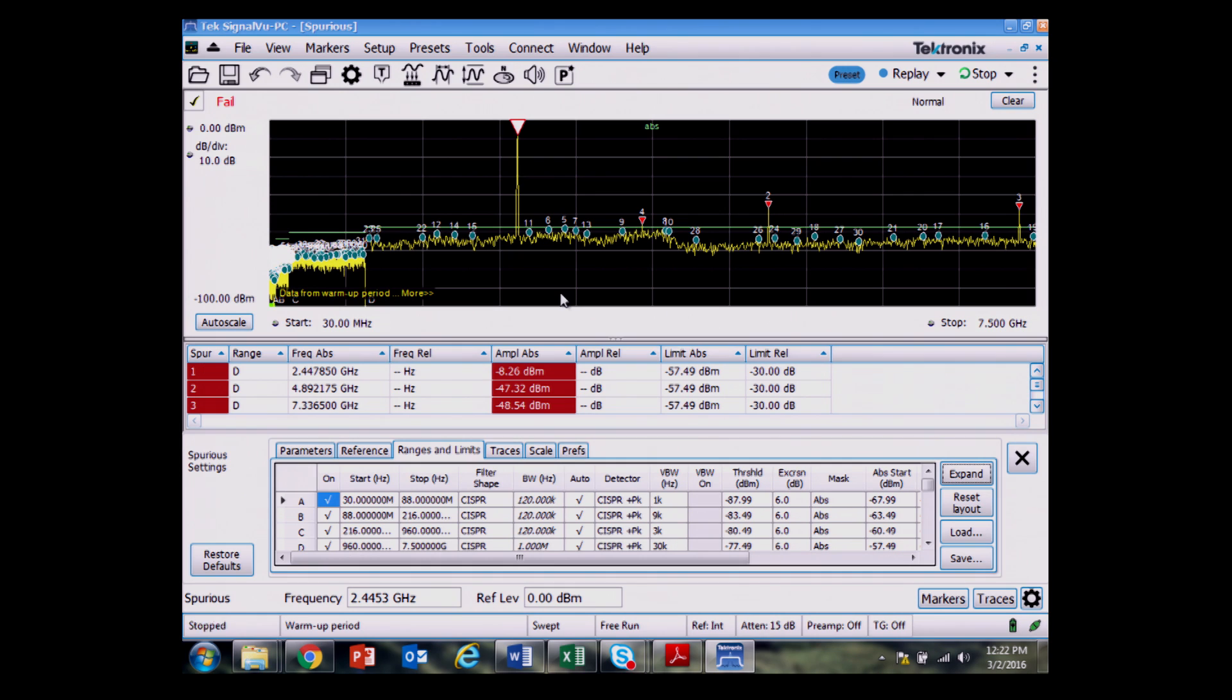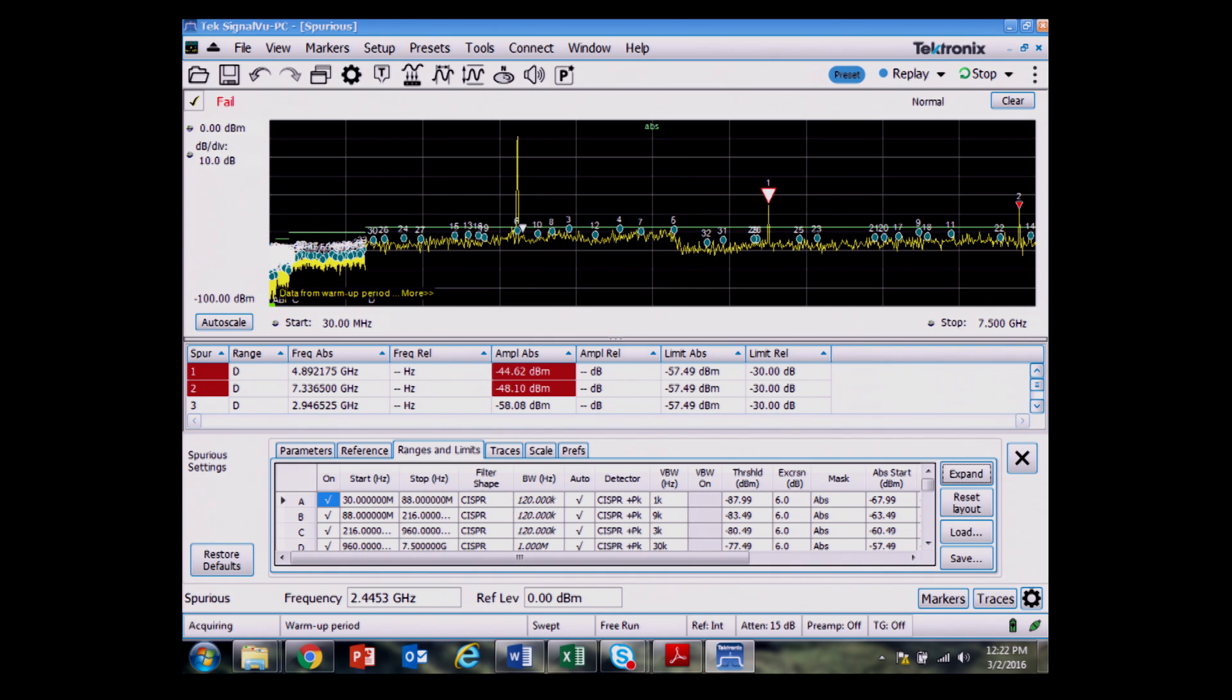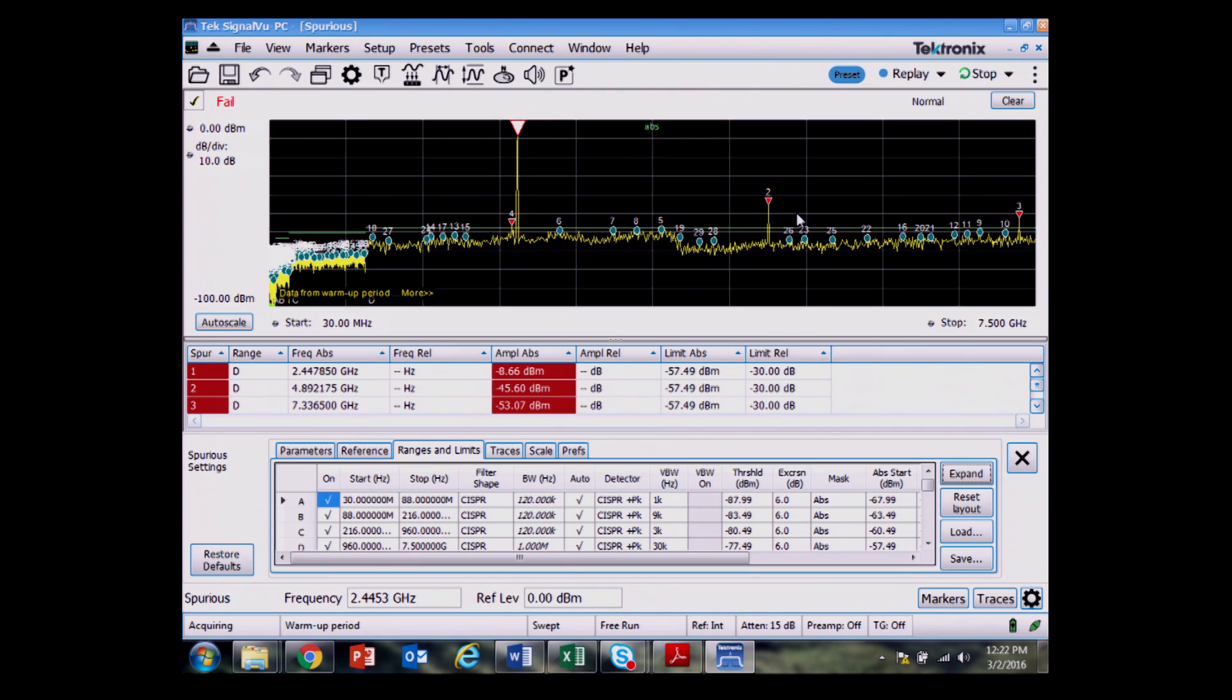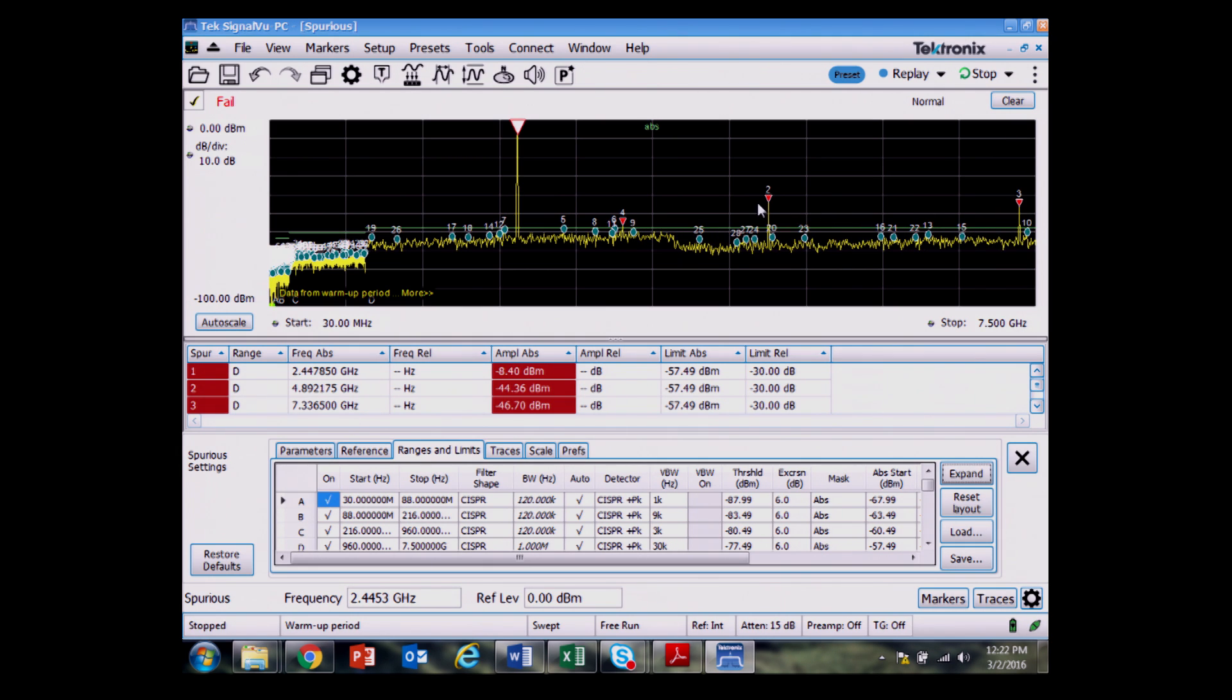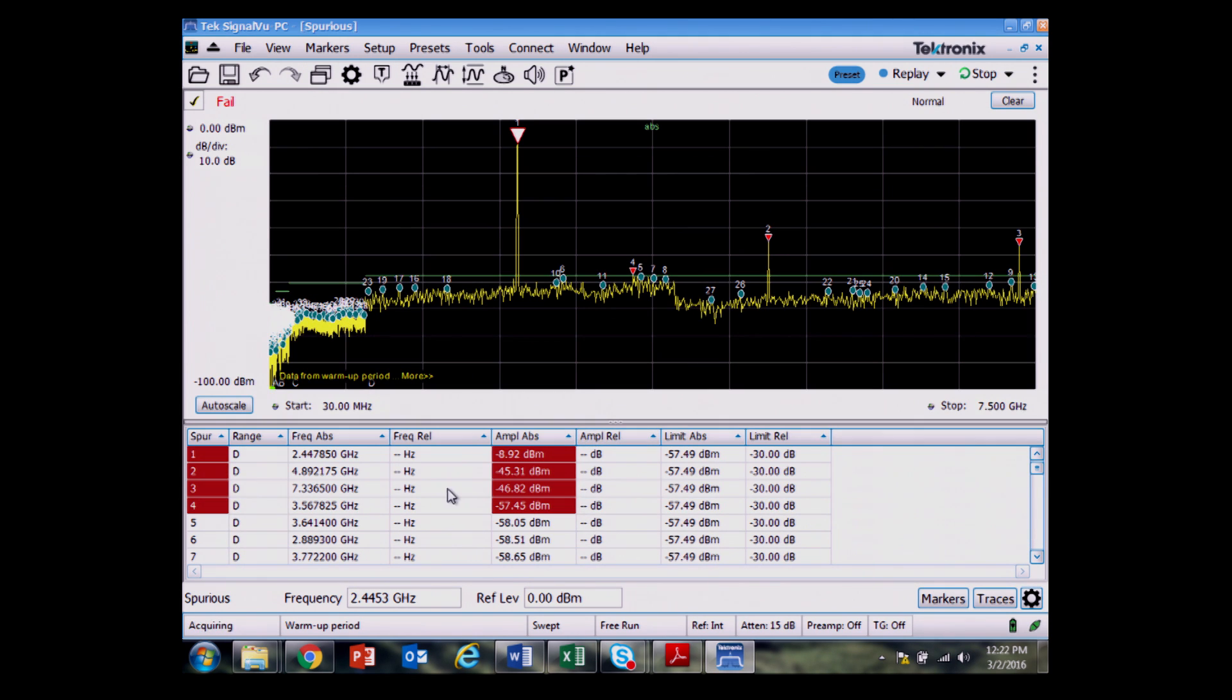So I'm failing the test. I really need to redraw this limit line to exclude the ISM band, the 80 MHz ISM band. But I have a couple of spurs on this device up at these higher frequencies, which are a failure, and all of those are listed in the table which appears below the spur search.